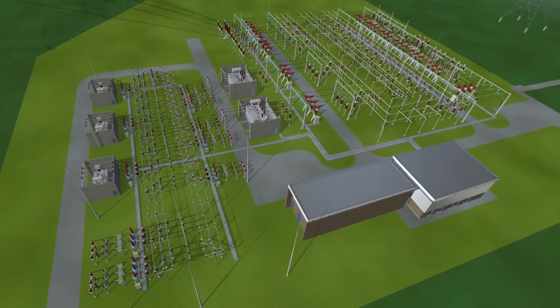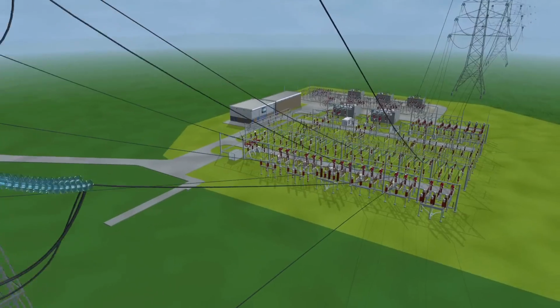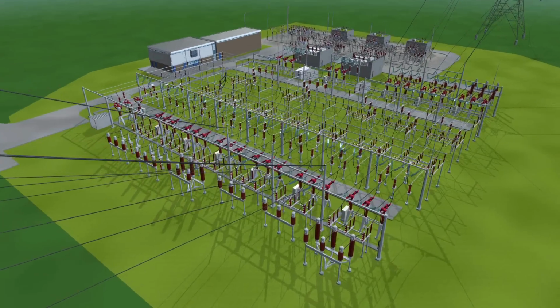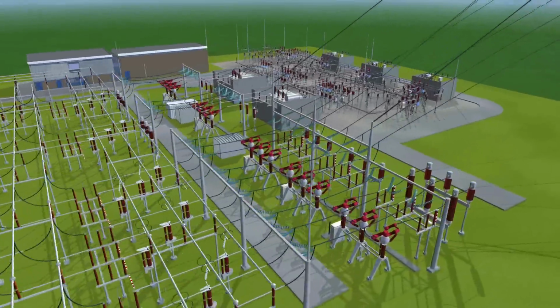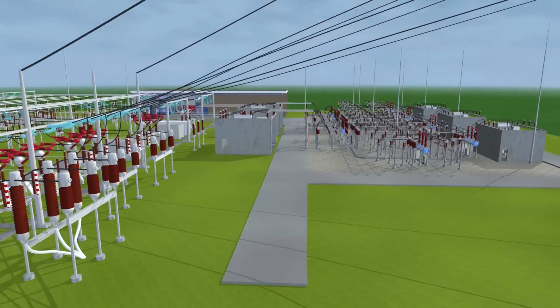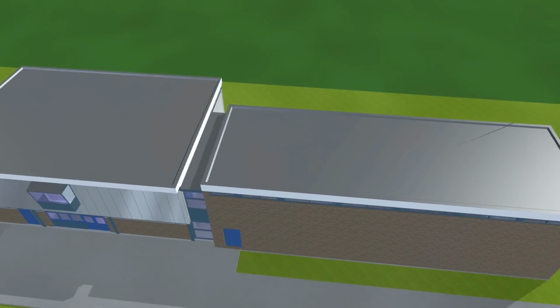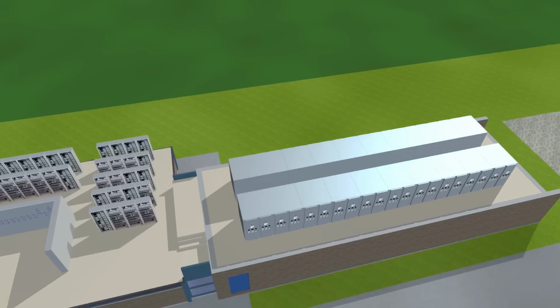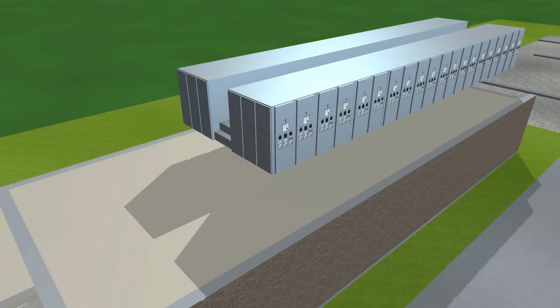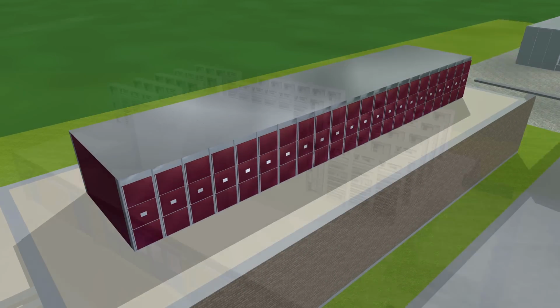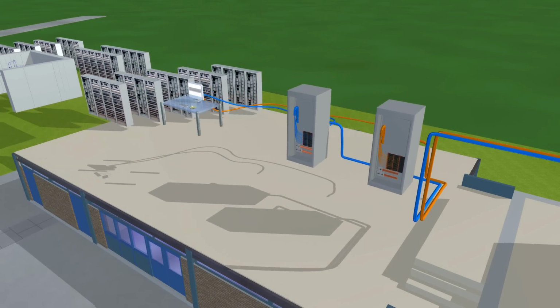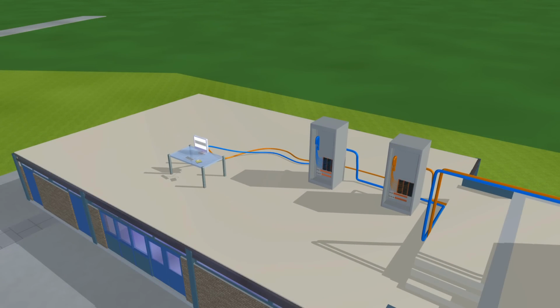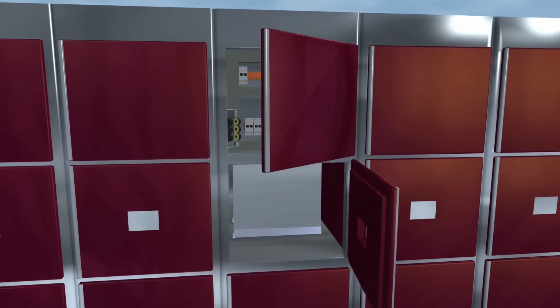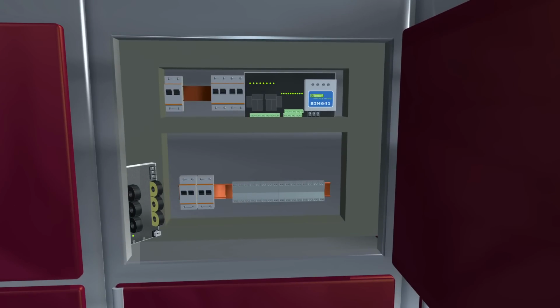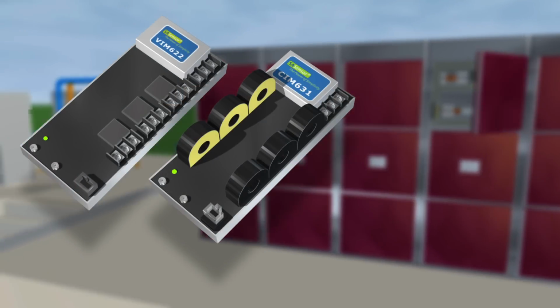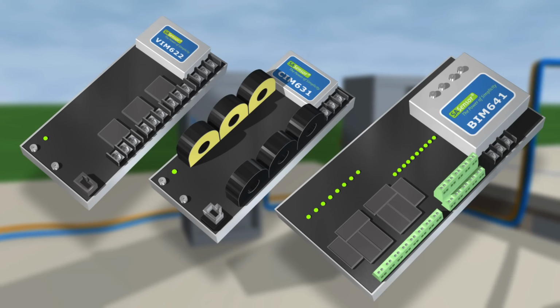In these substations, the voltage is converted from high voltage, usually 150 kV, to medium voltage, 10 or 20 kV. The energy comes in at the high voltage installation. This is made up of cables, switches, and a busbar construction. The secondary installation measures, controls, and protects. Its former analog components are now replaced by the digital computer-driven SA sensor system. The SA sensor's measuring modules on the feeding and outgoing 10 kV bays continually measure the voltage and the current. At the same time, the system ensures the safety and operation of the electricity network.